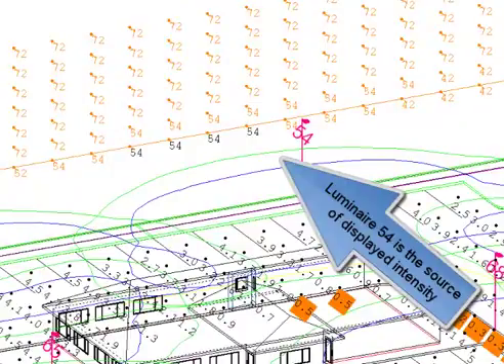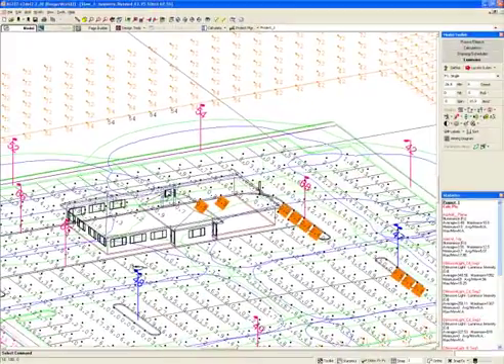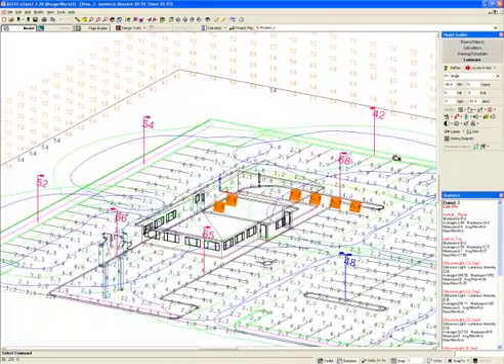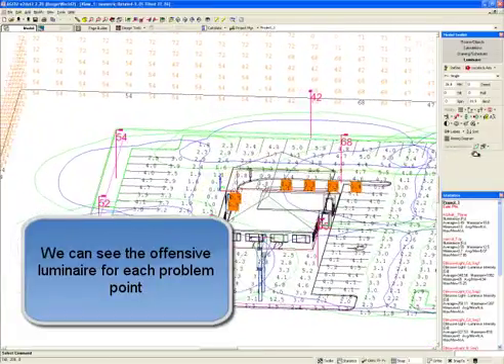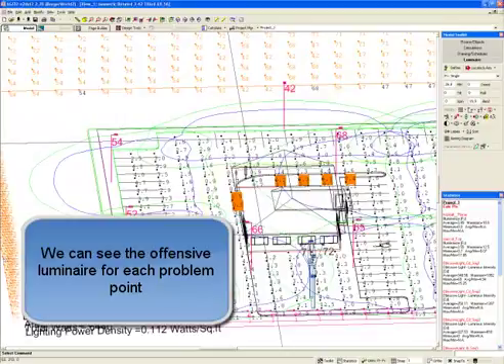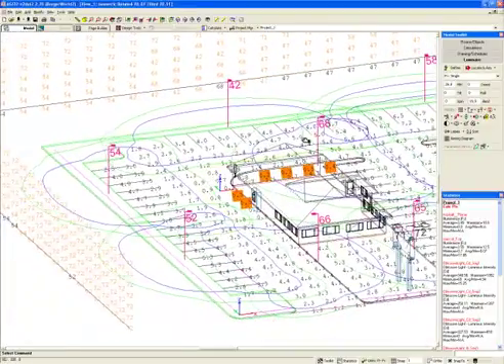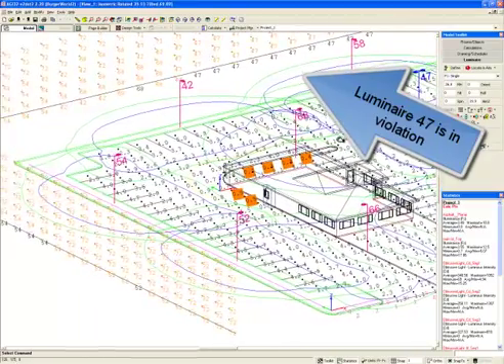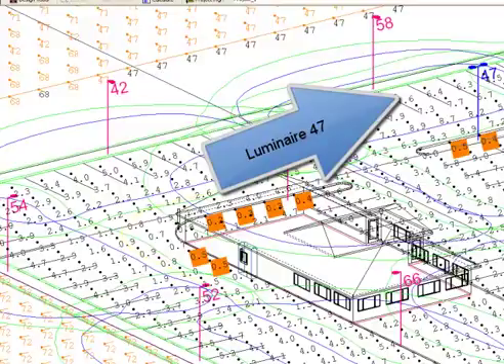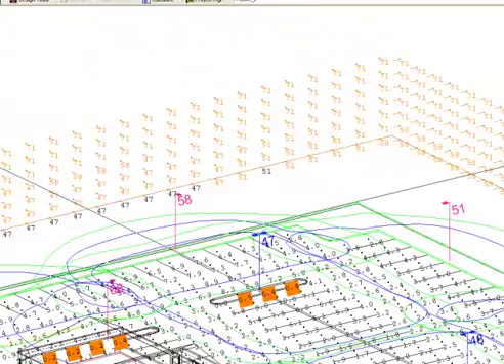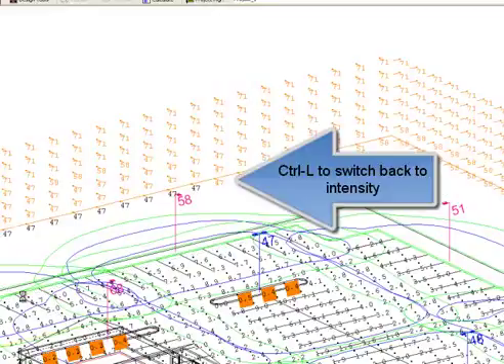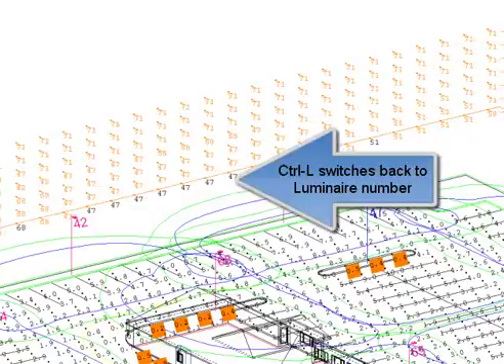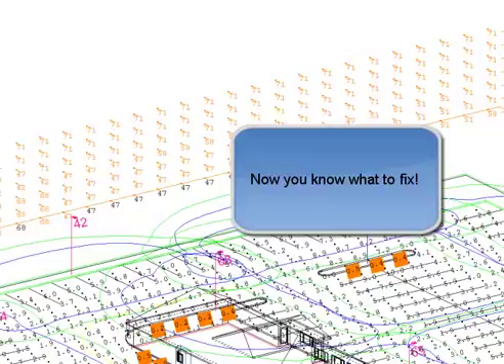Luminaire 54 is the source of displayed intensity. Panning around, we can see the offensive luminaire for each problem point. Luminaire 47 is in violation. There's luminaire 47. Control L to switch back to intensity. Control L again switches back to luminaire number. Now you know what to fix.